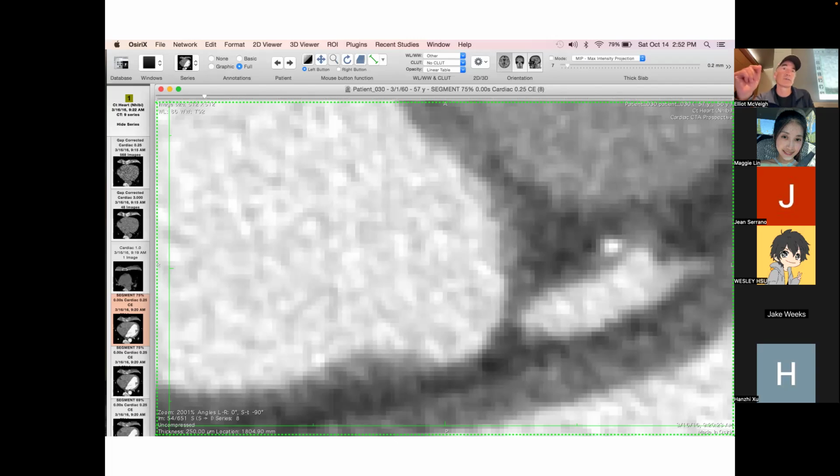So that's sort of an estimate of what the spatial scale is of the resolution that we're dealing with. But we all know, because we're good engineers, that that isn't the spatial resolution of the imaging system. The spatial resolution is given by the point spread function and the modulation transfer function. Either one of those, right? Not by the voxel dimension, right? You should match the voxel dimension such that it makes sense.